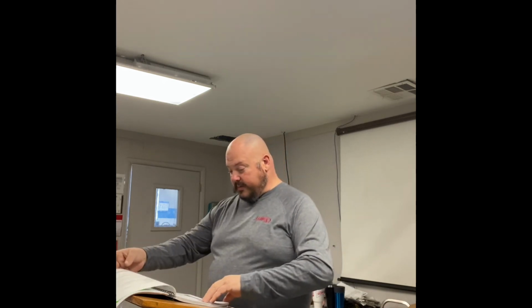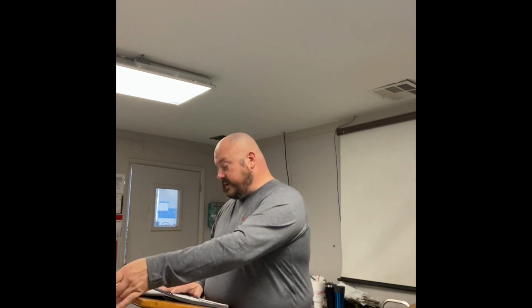Duh, right? So I'm going to tell you that, first of all, read the directions for each one before you start using it. There's different directions, there's different models, there's different manufacturers. Danfoss is one of the biggest ones. You're going to be looking at that, and you're going to be trying to understand how to do it. You're going, oh, well, you take the bottom cap off, and oh, okay, great. Well, if you don't get that all nice and sealed up, you got a leak. Make sure you seal it up and get it nice and tight when you put it back together. Don't damage the O-rings. If you do, replace them. Pretty simple. Okay.